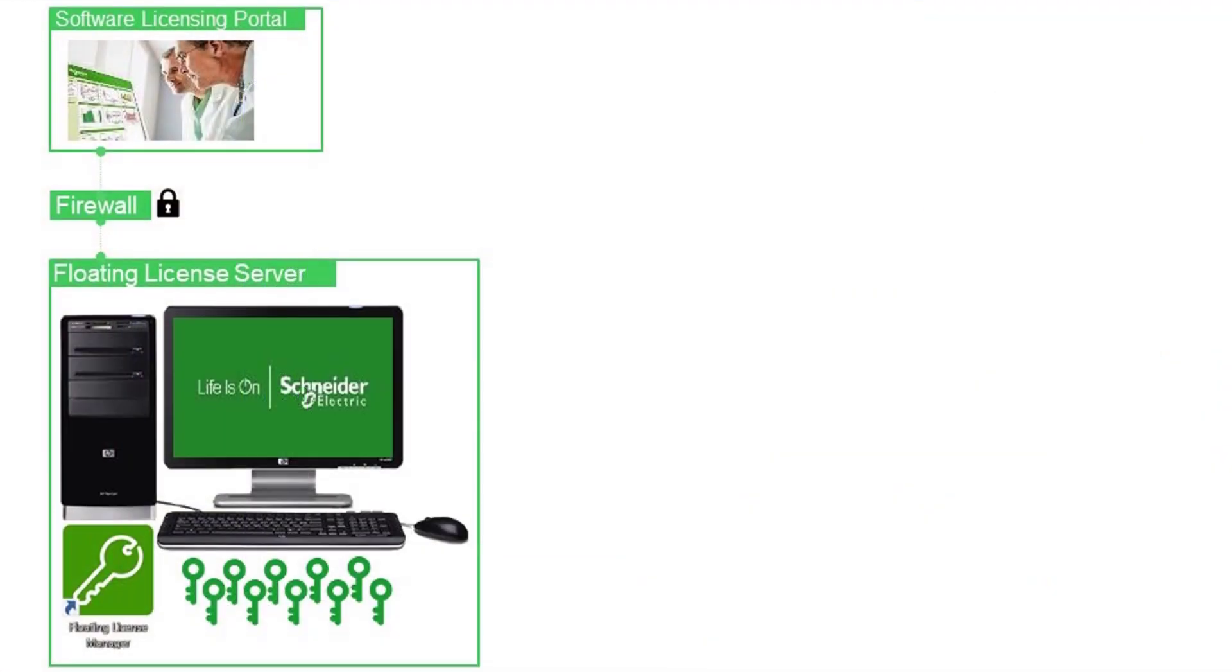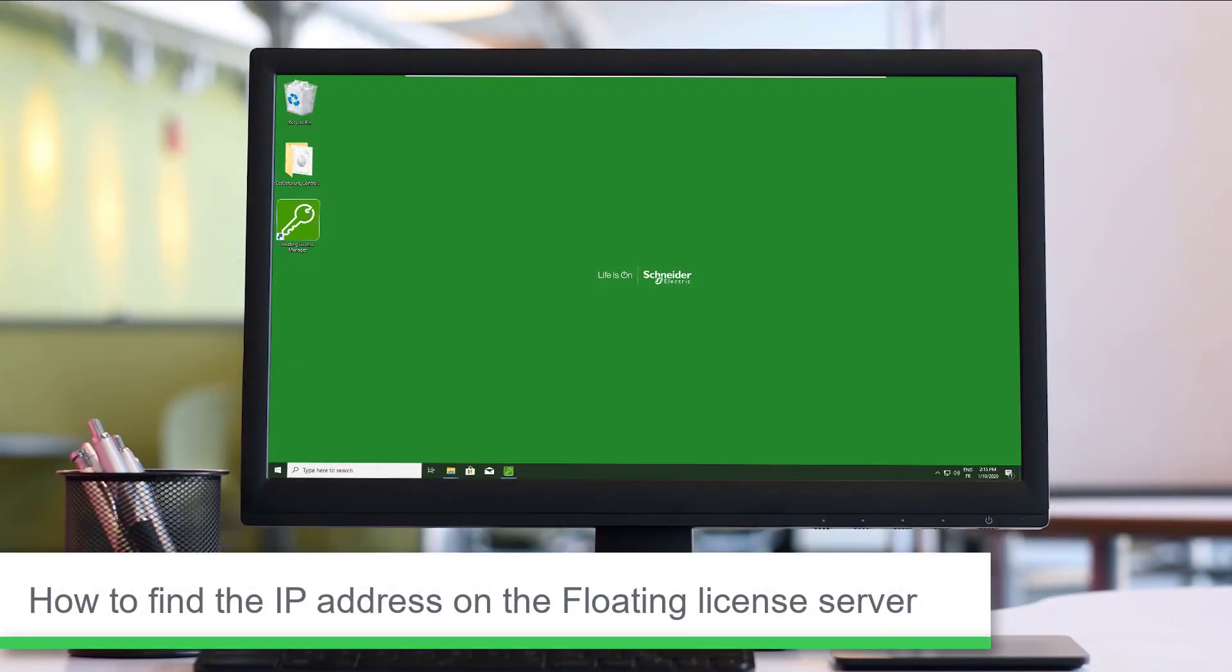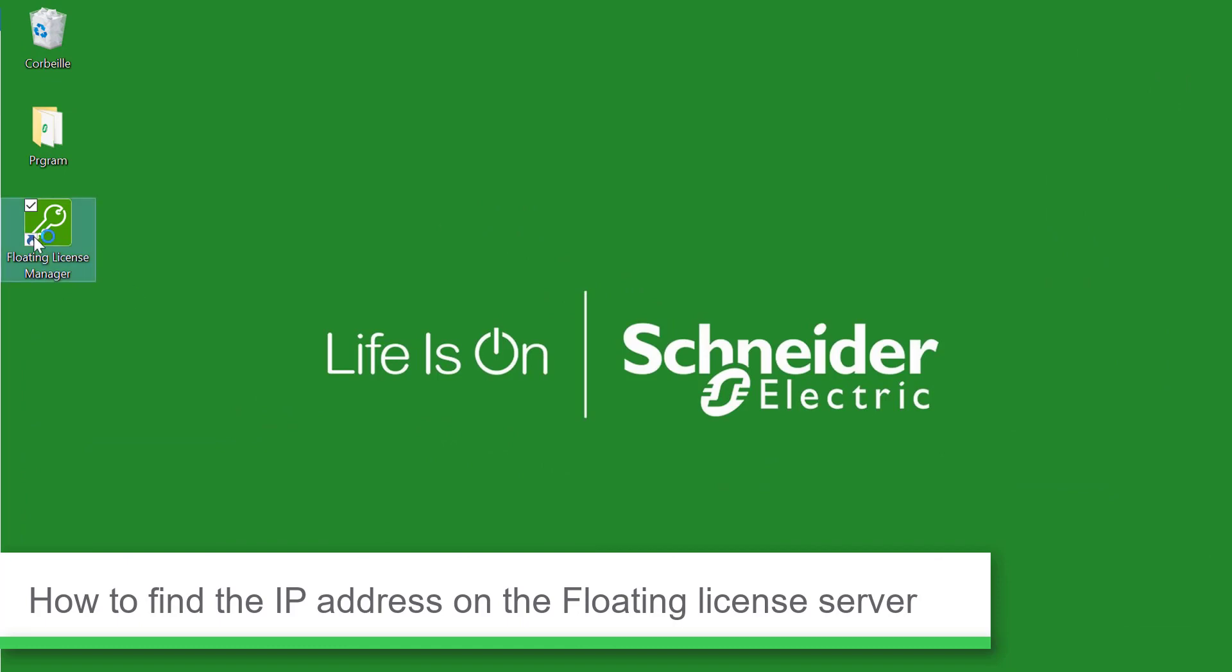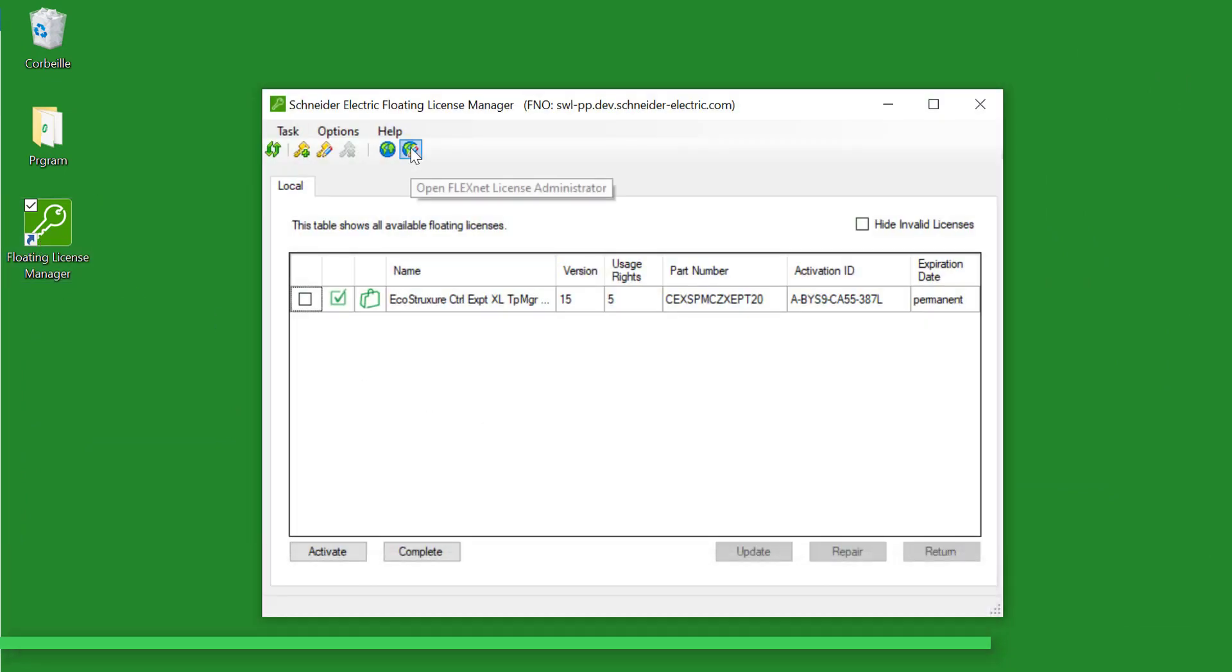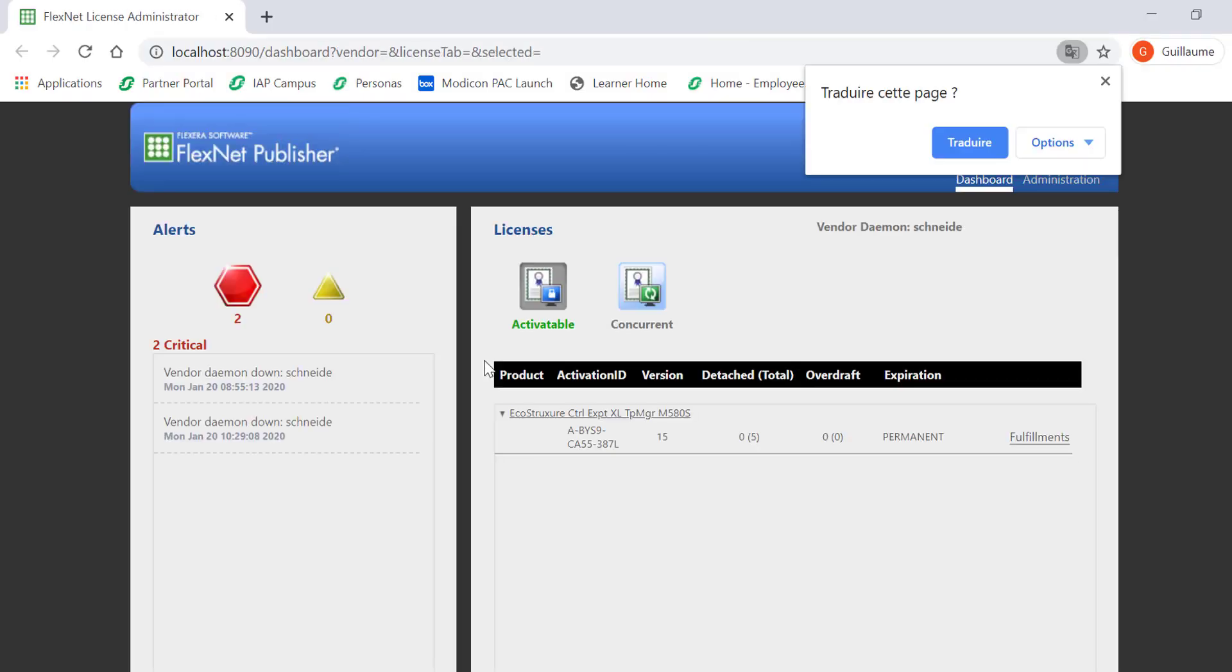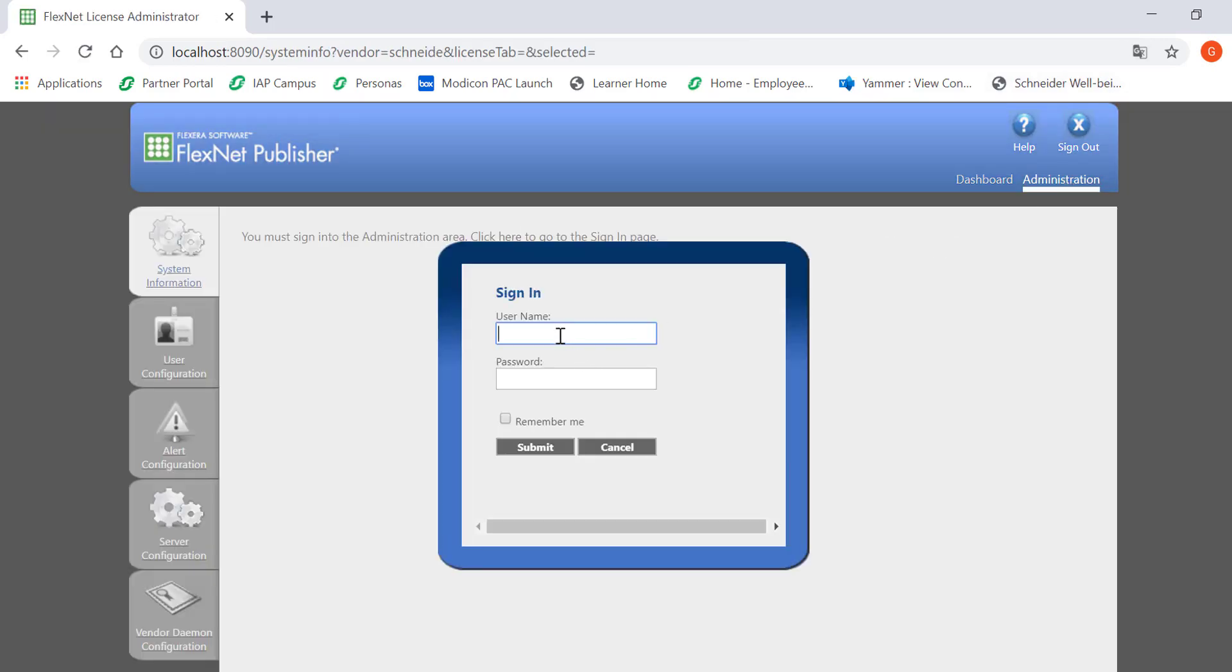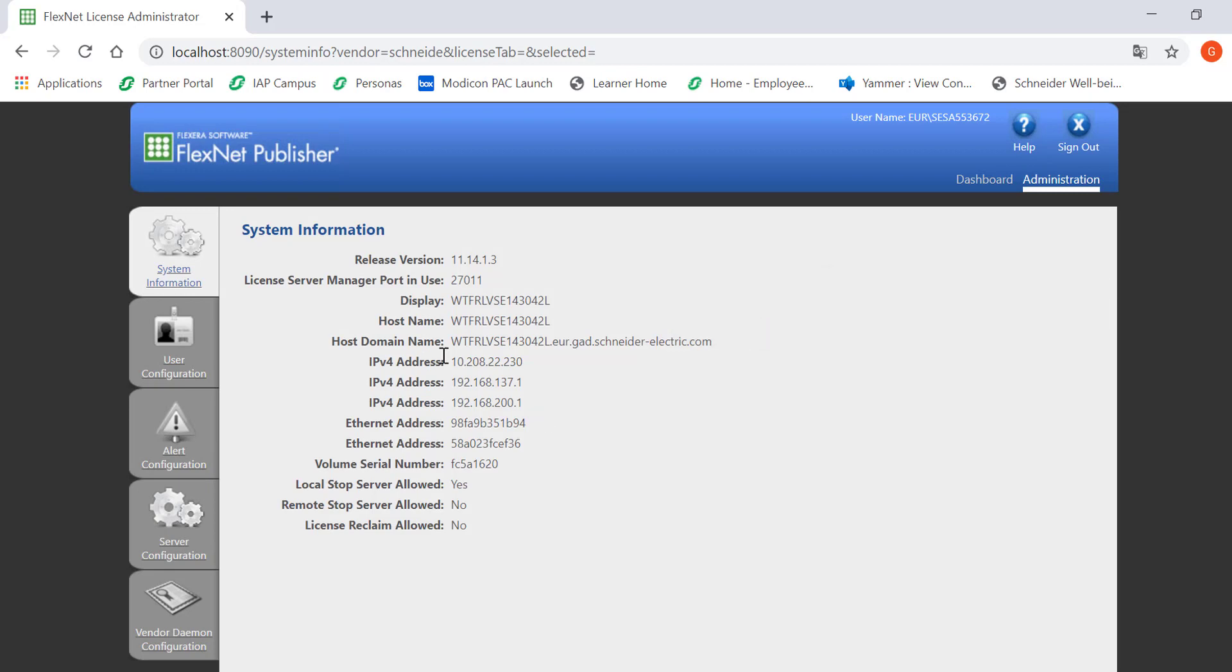If you didn't know those data, go on the floating license server and open FlexNet by clicking on the second Earth icon. Click on the Administration tab and login with the Windows domain user account of the user who has installed the Schneider Electric floating license manager. The right IP address is the first IPv4 address from the System Information tab.